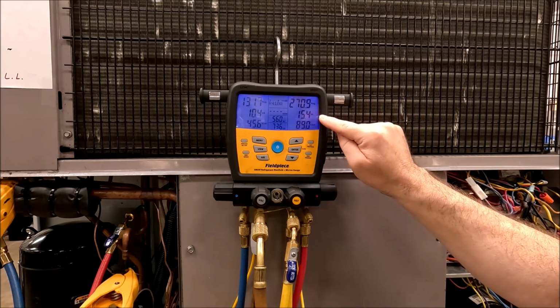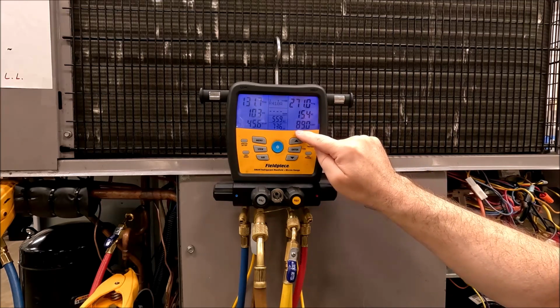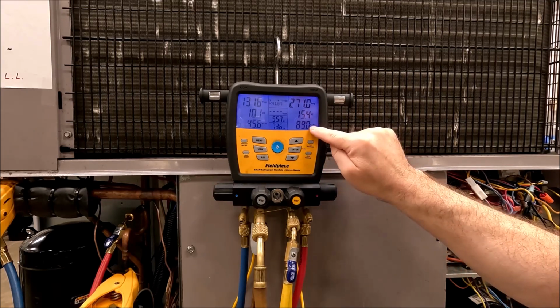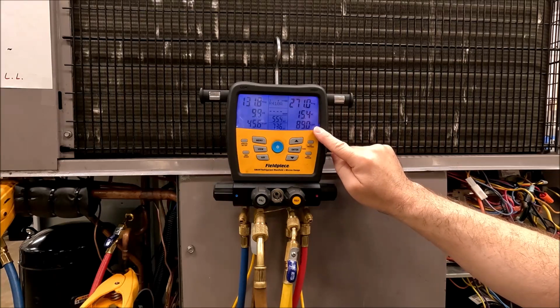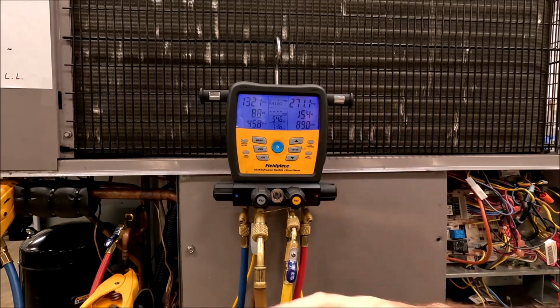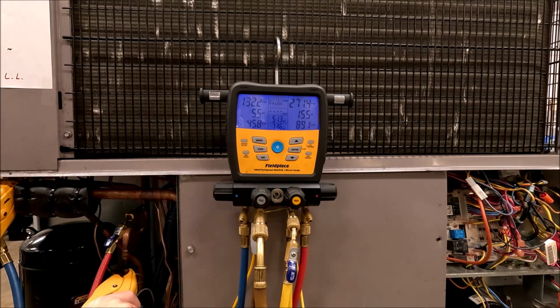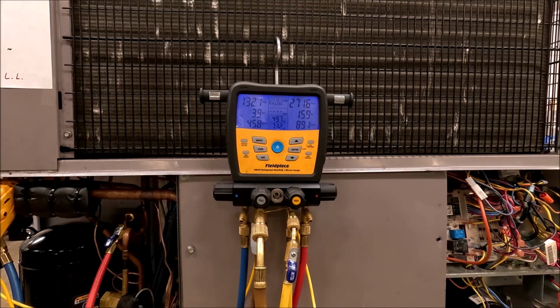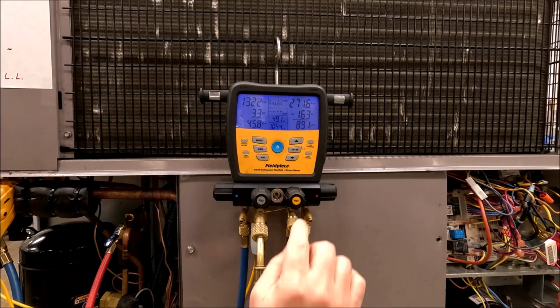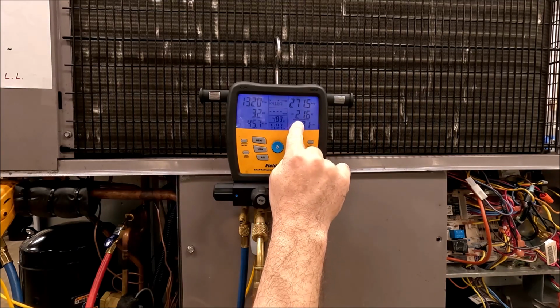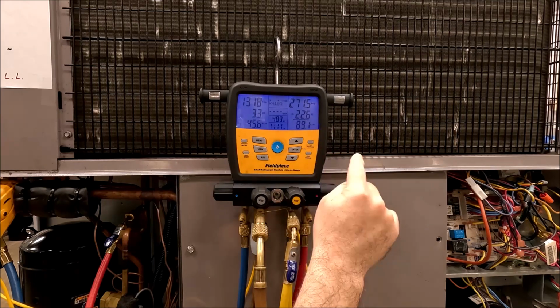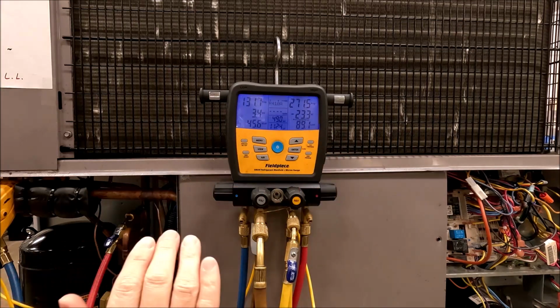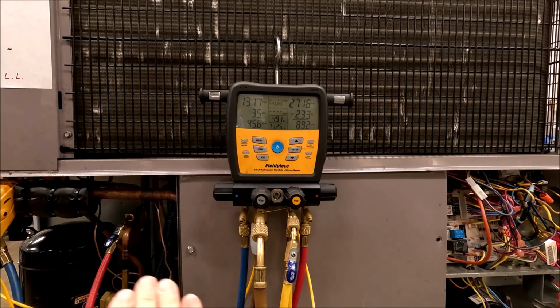So it knows positive 15 right here. The liquid line is 15 degrees colder than your liquid saturation point. So we've got a liquid line somewhere around the 75 degree mark. Watch what happens if I put it on the discharge line. Watch our subcooling numbers. Oh man, it's going negative hard, right? So minus 22, it says below typical range. There is no negative subcooling or negative superheat.